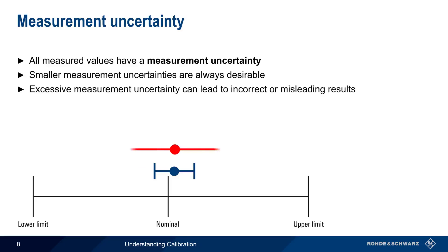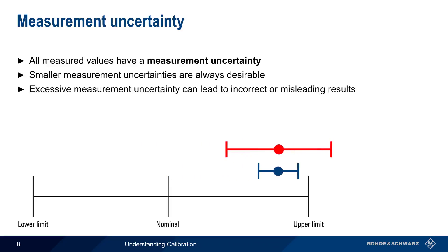A measurement with a much larger uncertainty, due to a poorly or uncalibrated instrument, may still produce acceptable results when the measured value is near the nominal value, as shown here. But when the measured value is close to the upper limit, the larger measurement uncertainty can lead to erroneous results, such as declaring something out of range when the true value falls within the limits. Properly calibrated instruments have lower measurement uncertainty, and therefore minimize the probability for different types of error.